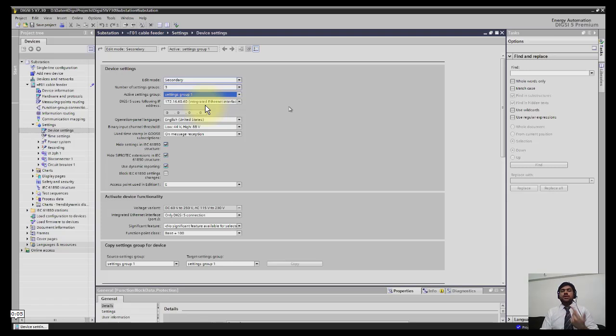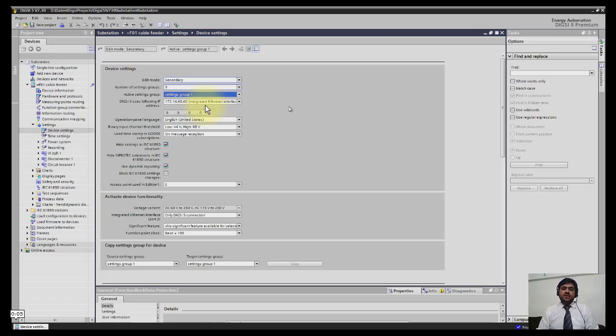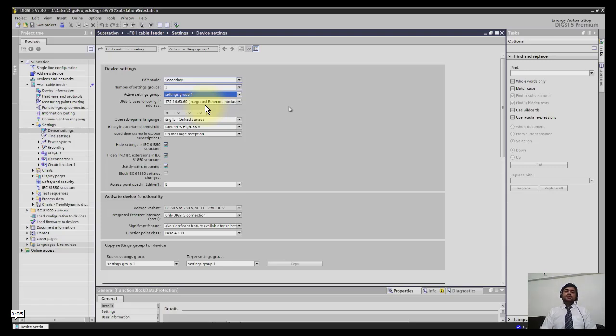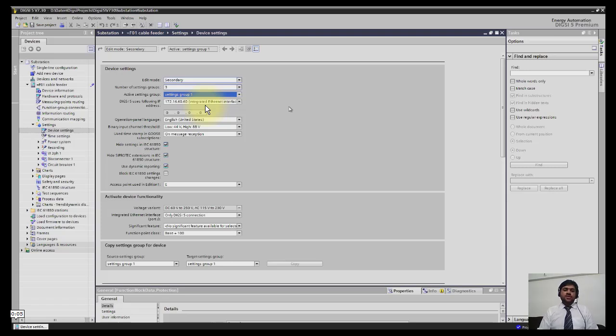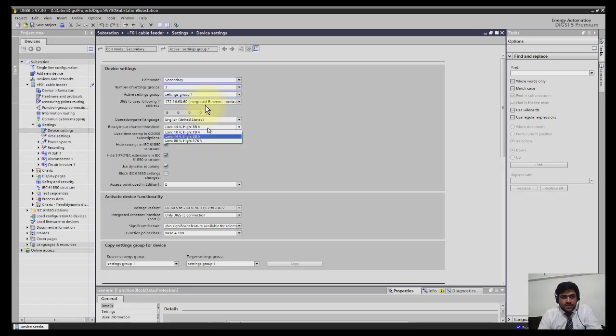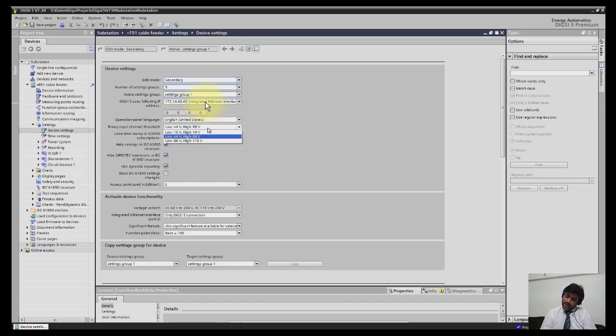The example could be, for example, in certain areas there are two settings provided for winter and summer timings. Winter and summer both have different types of loads, so you can choose by some binary input to change the complete setting group.